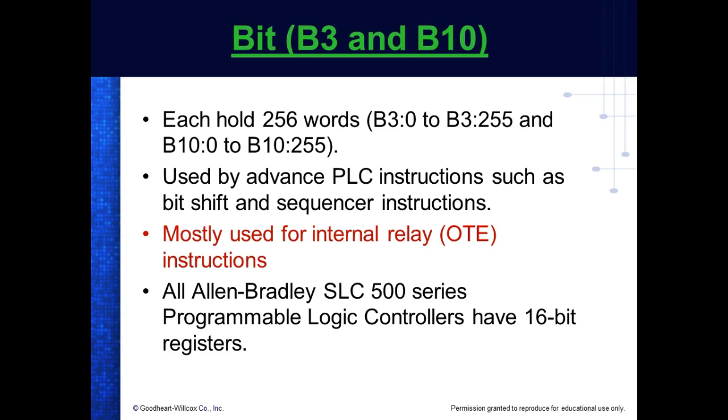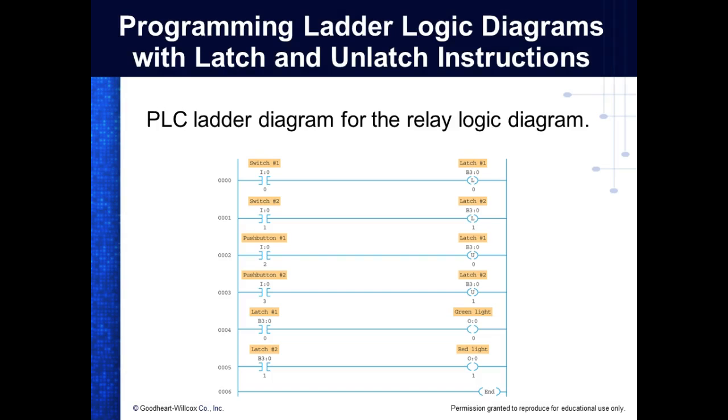In a true motor control circuit, probably 80 to 90% are not driving power. They're not a power circuit. It's just a control circuit. And what we find out is that we can program every bit of the control circuit into the PLC. And if it does not require an output, then we don't need to sacrifice one of our outputs. This guy right here has only got 6. And if I use something for a relay that never needs a contact outside my program, I sacrifice one of my output ports.